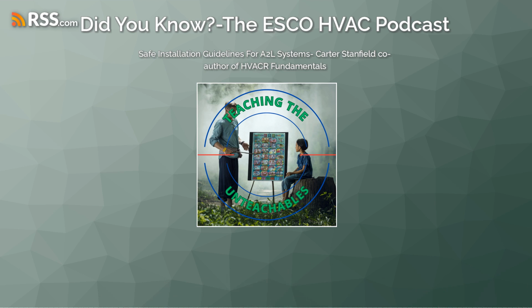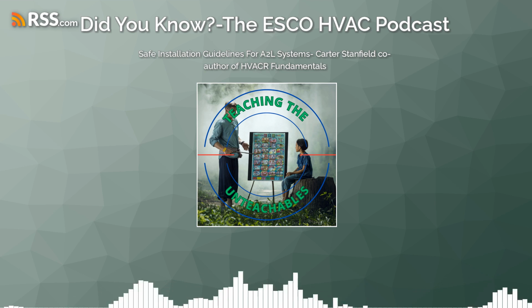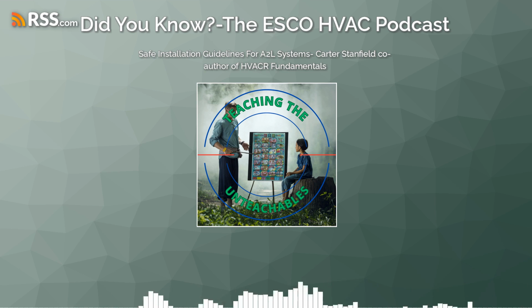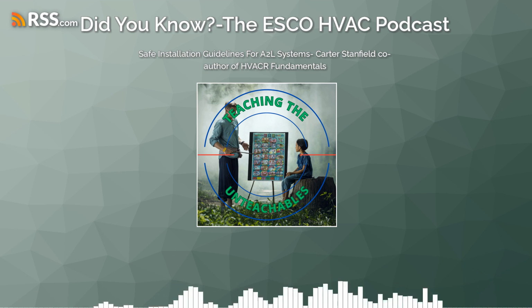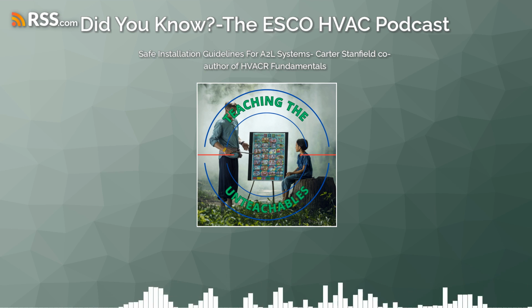So until recently, the standard ASHRAE 15 would not allow flammable refrigerant in a high probability system. So the first allowance of any kind of flammable refrigerant in a high probability system came about in the 2019 revision of the ASHRAE Standard 15.